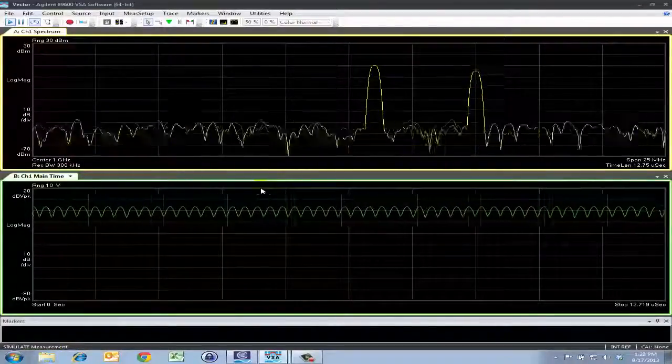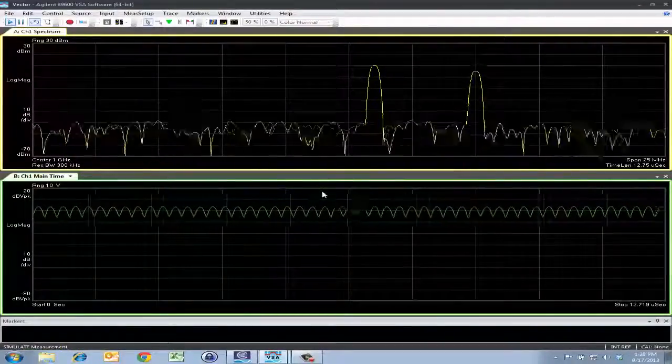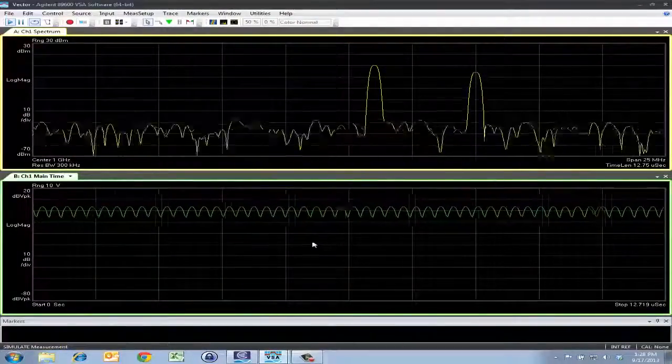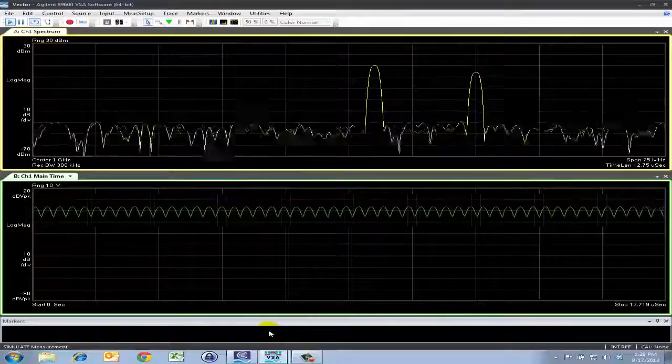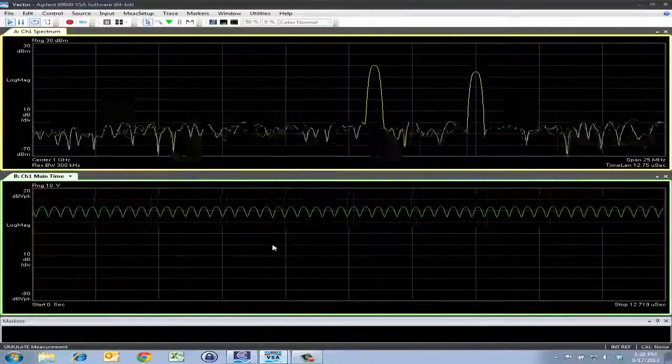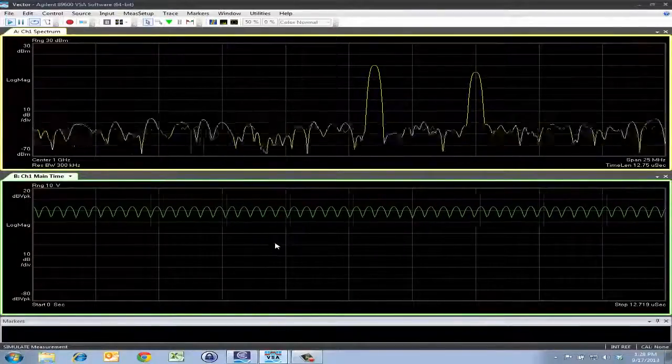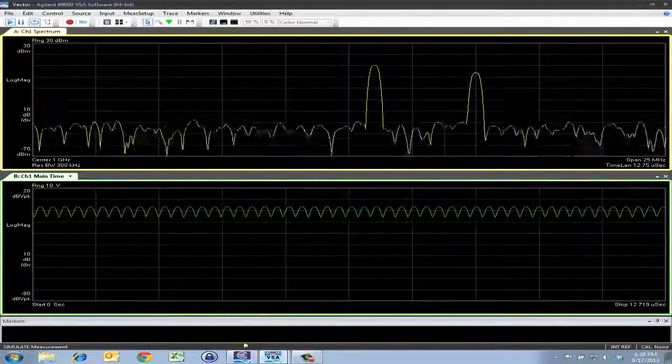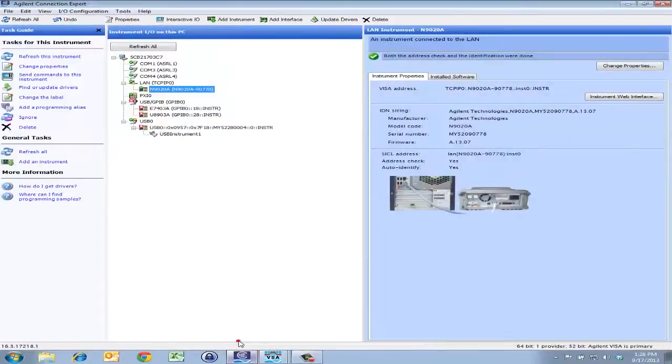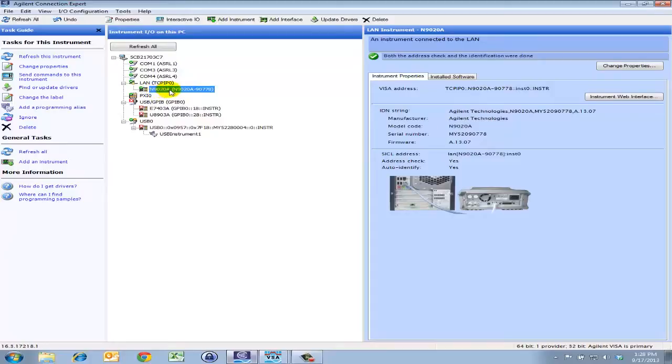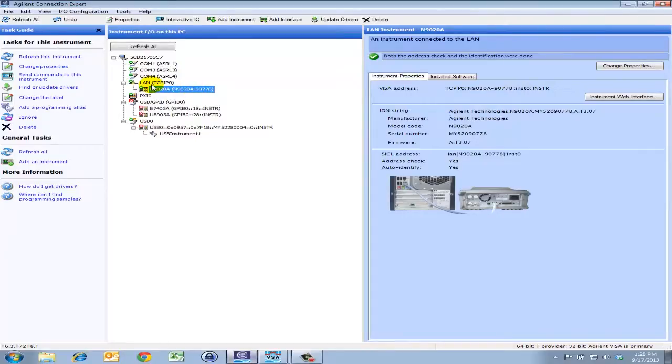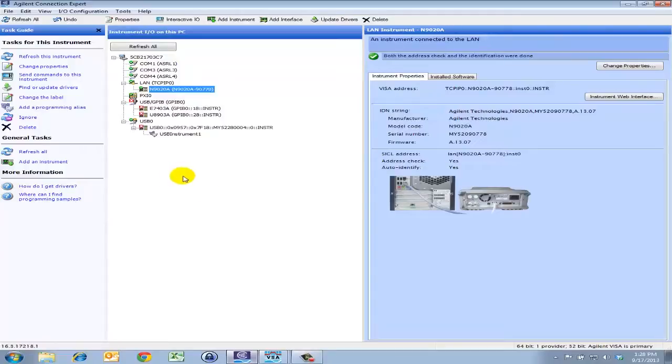So let's get started. First thing that we want to do is to make sure that our hardware is connected in the Agilent Connection Expert before the VSA software had started. In this example, I have already established a connection with an N9020A MXA analyzer. You can see that I'm connected through the host name. For more information and detailed instructions on how to get your instruments connected properly in the Agilent Connection Expert, please check out our Connectivity in IO Libraries demo video.